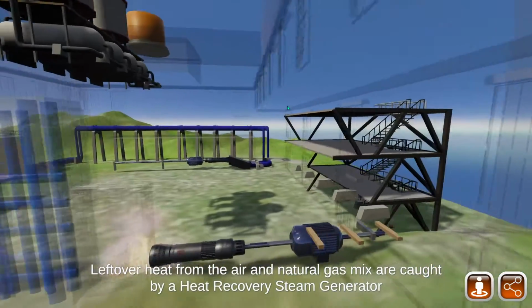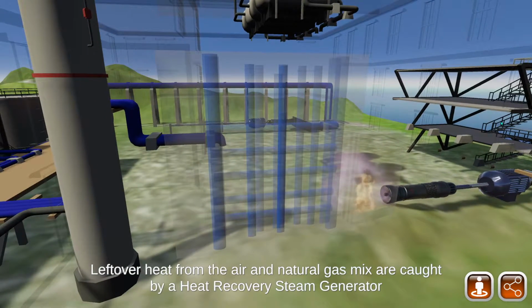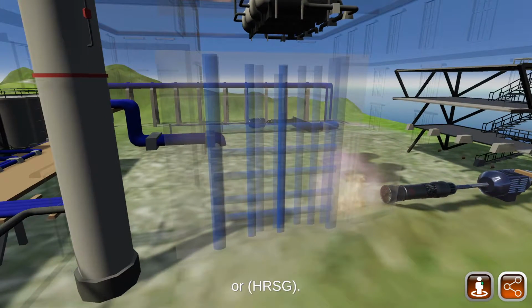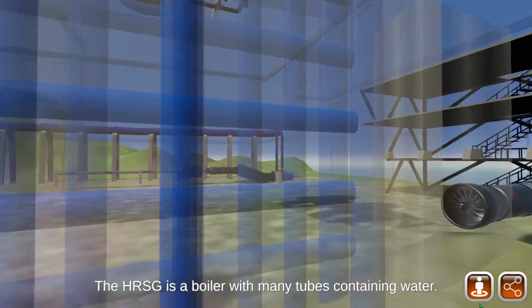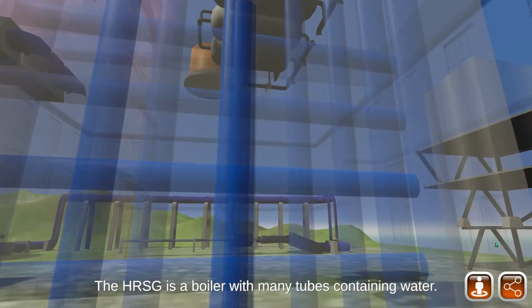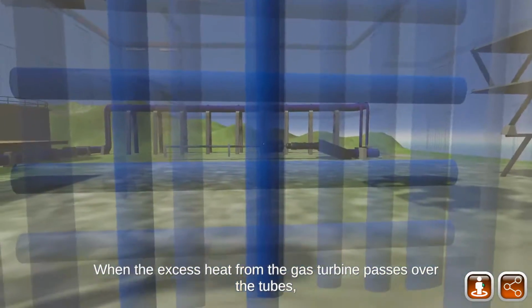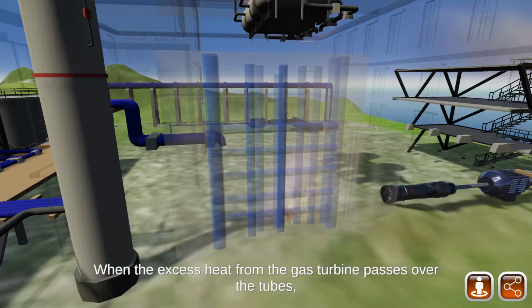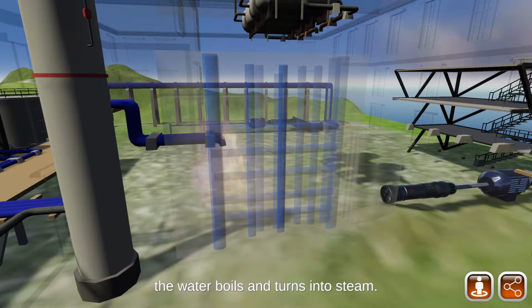Leftover heat from the air and natural gas mix are caught by a heat recovery steam generator, or HRSG. The HRSG is a boiler with many tubes containing water. When the excess heat from the gas turbine passes over the tubes, the water boils and turns into steam.